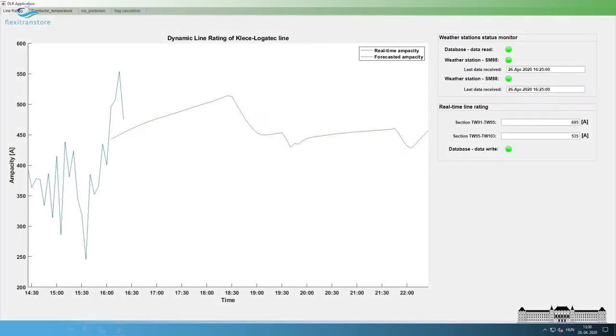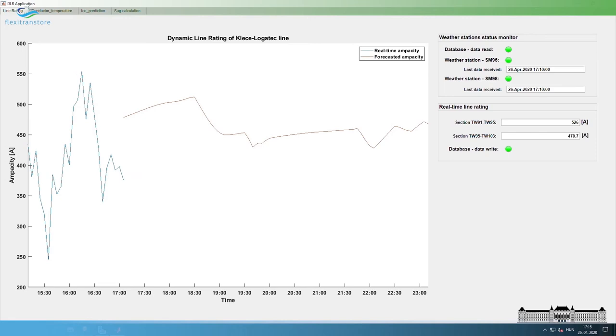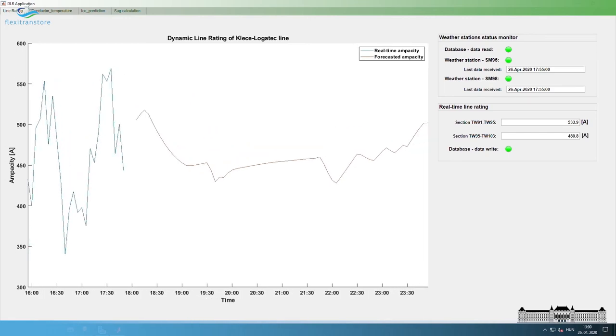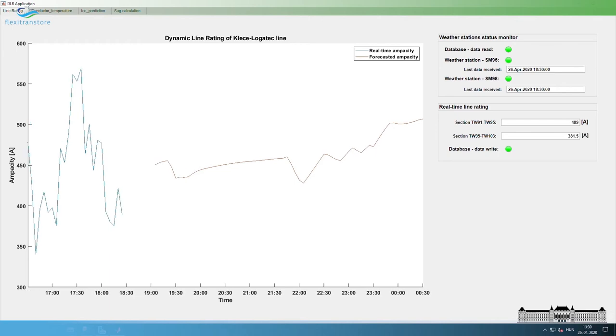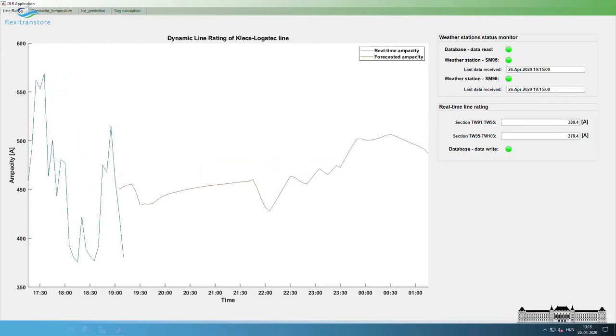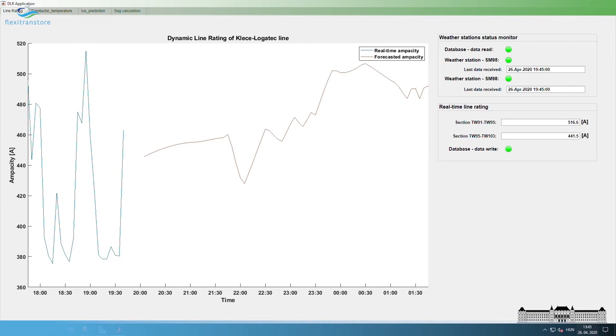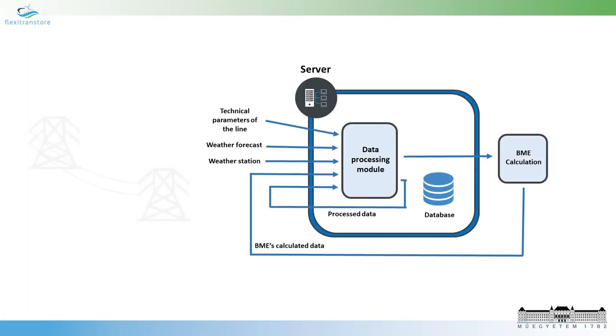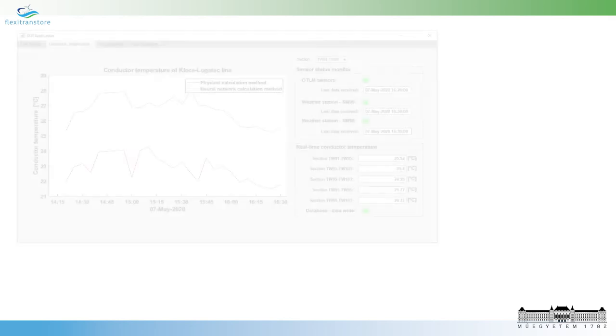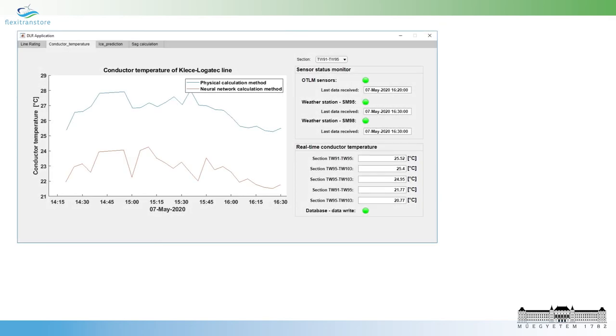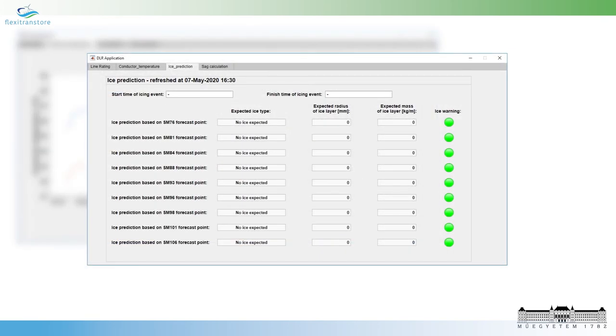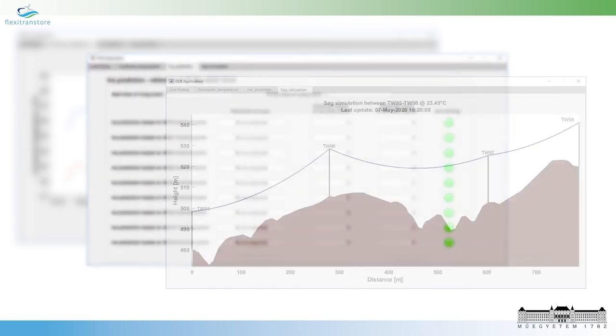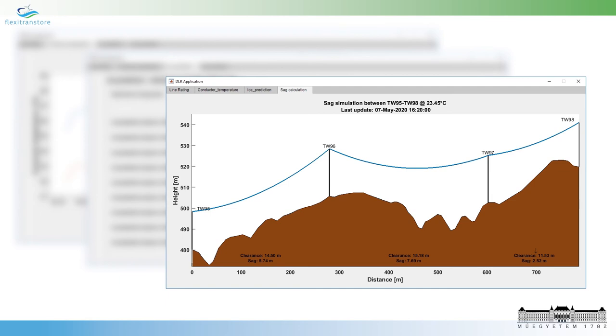The BME high voltage laboratory's DLR expert system was developed in order to monitor the actual thermal state of the conductors. For this purpose, the real-time and predetermined line ratings are calculated with an extended physical model. This model also takes the cooling effect of precipitation into account. The conductor temperature is also tracked by a neural network-based model. The ice prediction subsystem is developed in order to forecast possible icing events on power lines. For safe and high thermal utilization of the conductors, the SAG clearance calculation is also tracked by the grid management system.